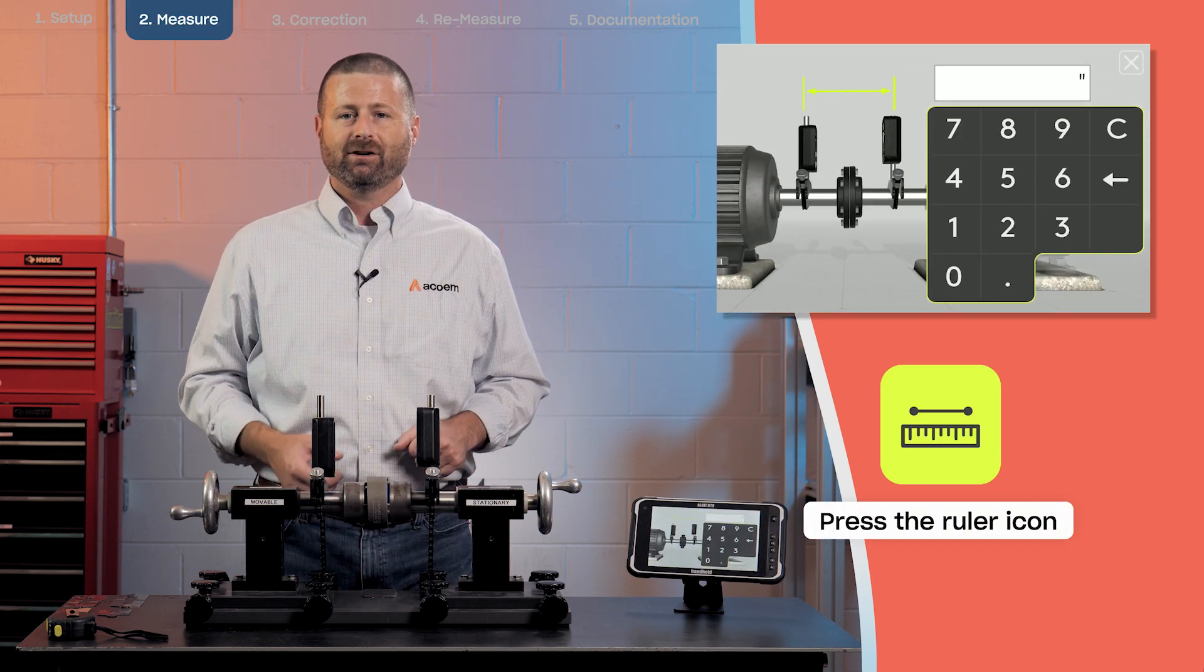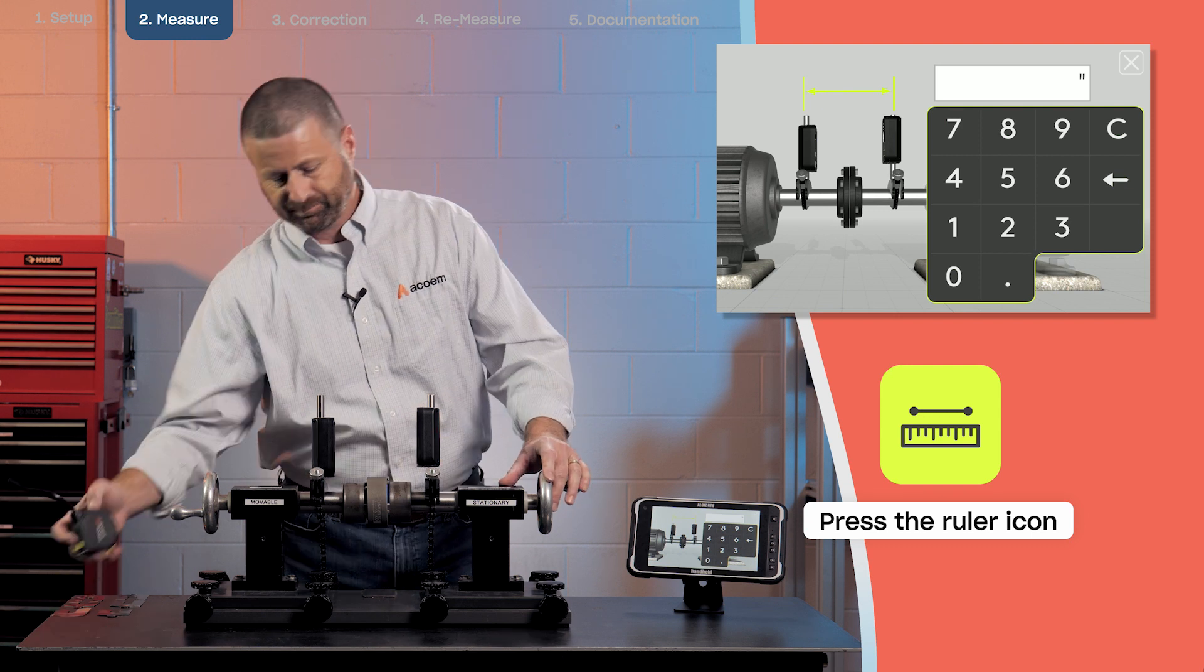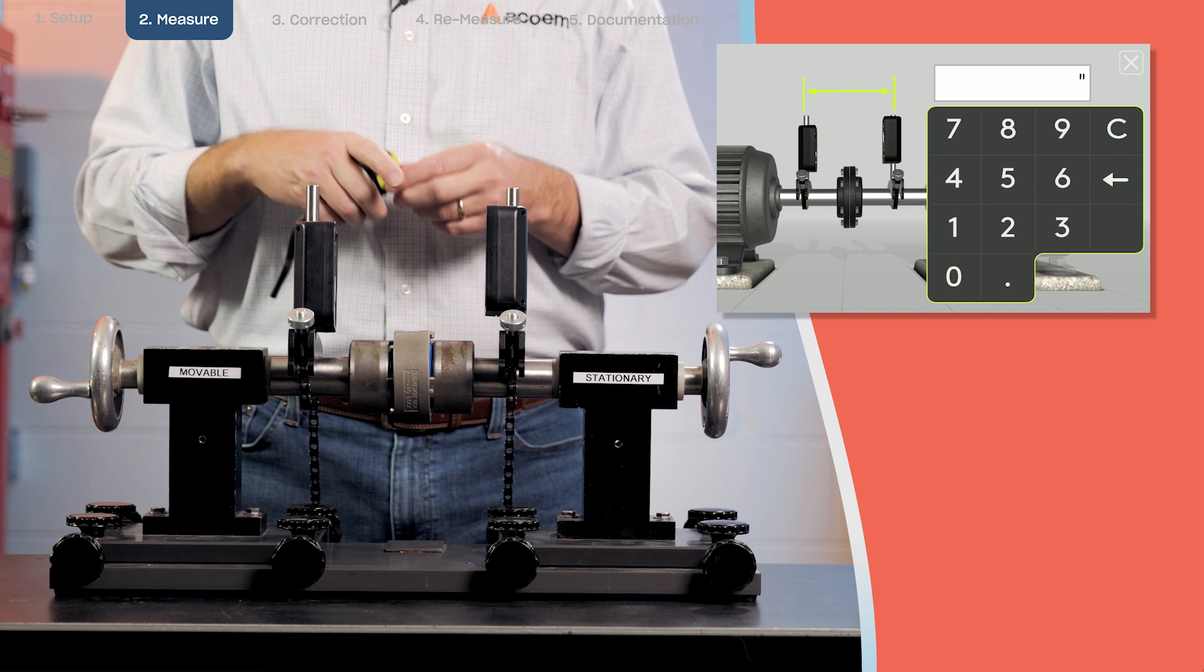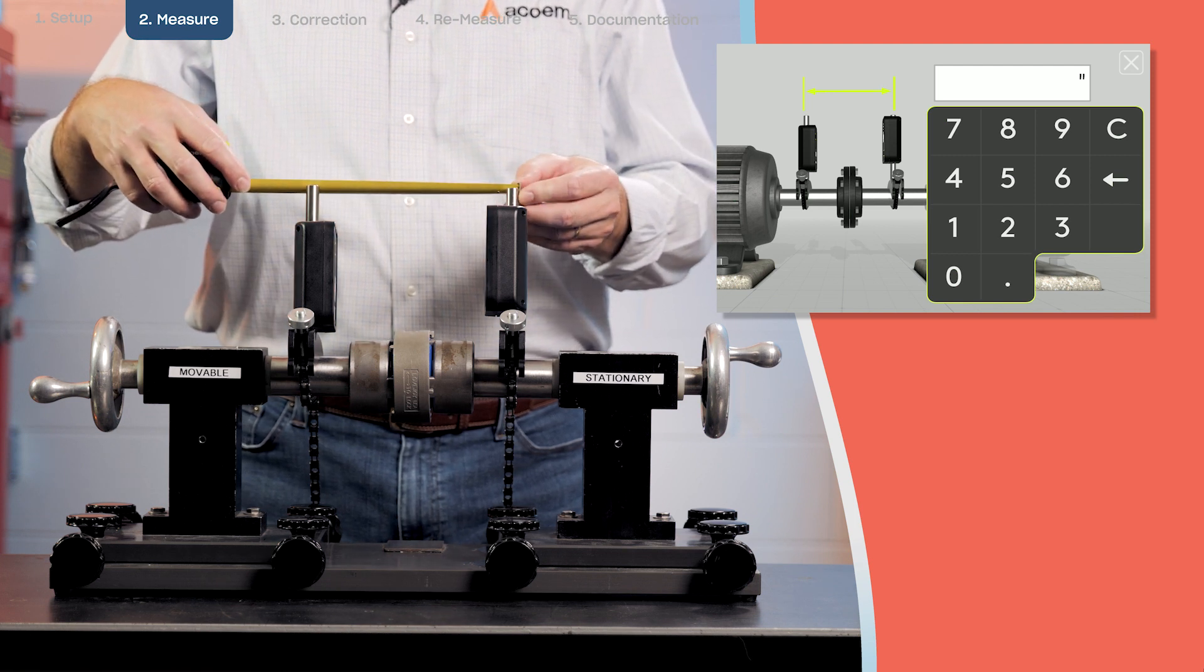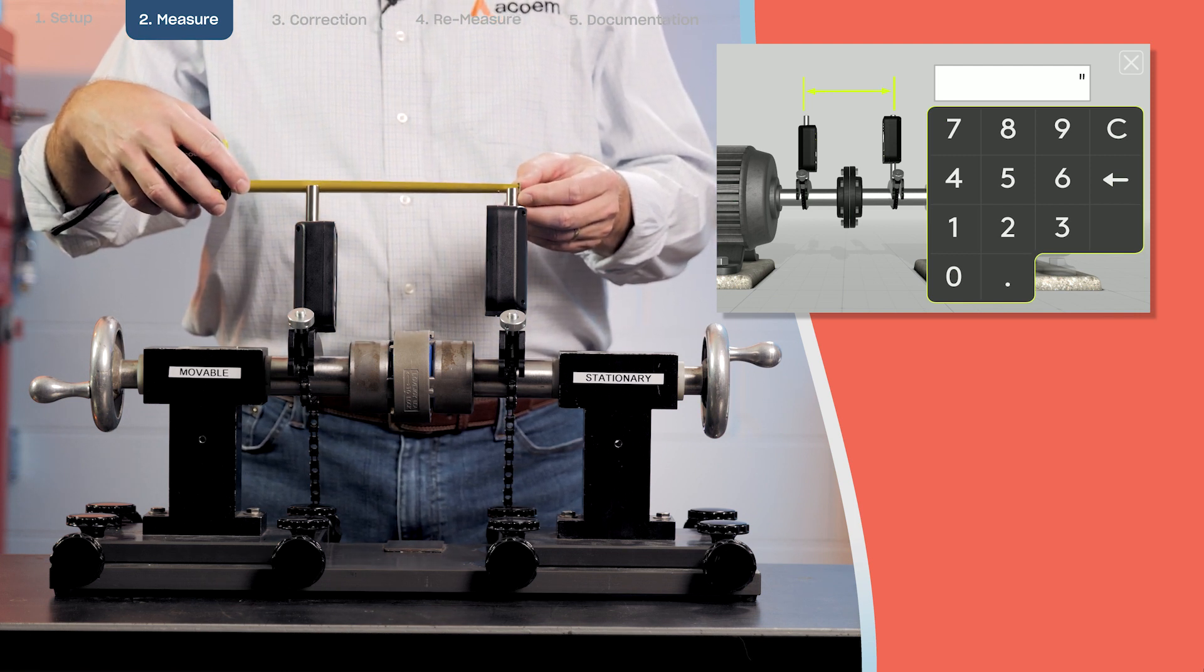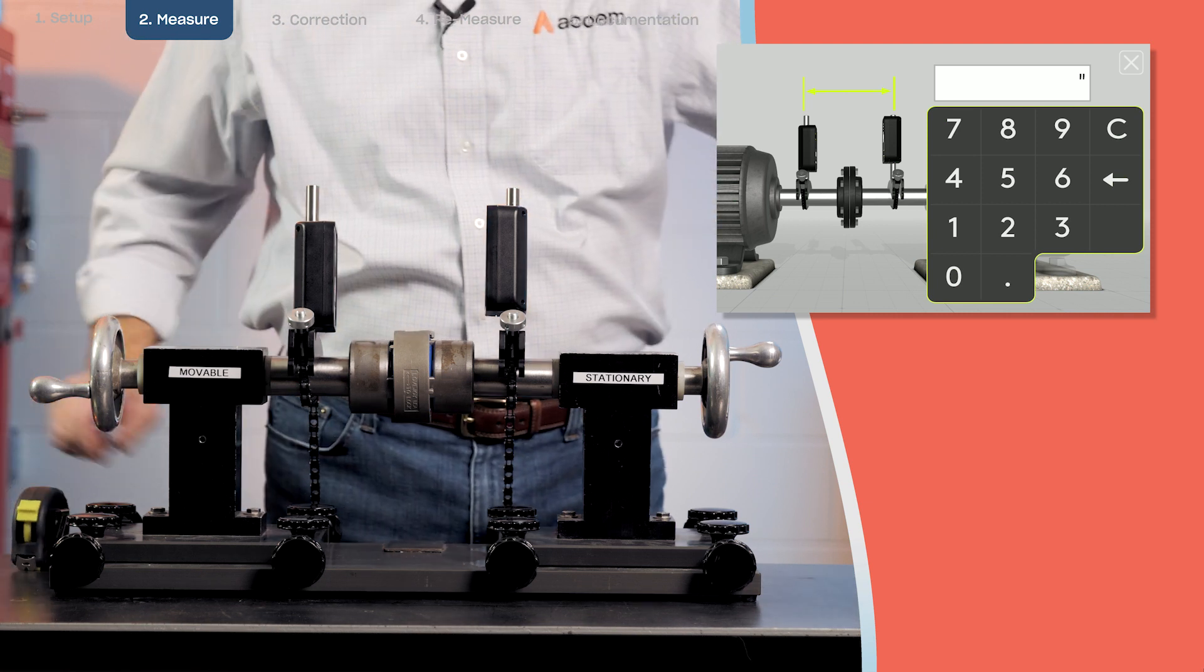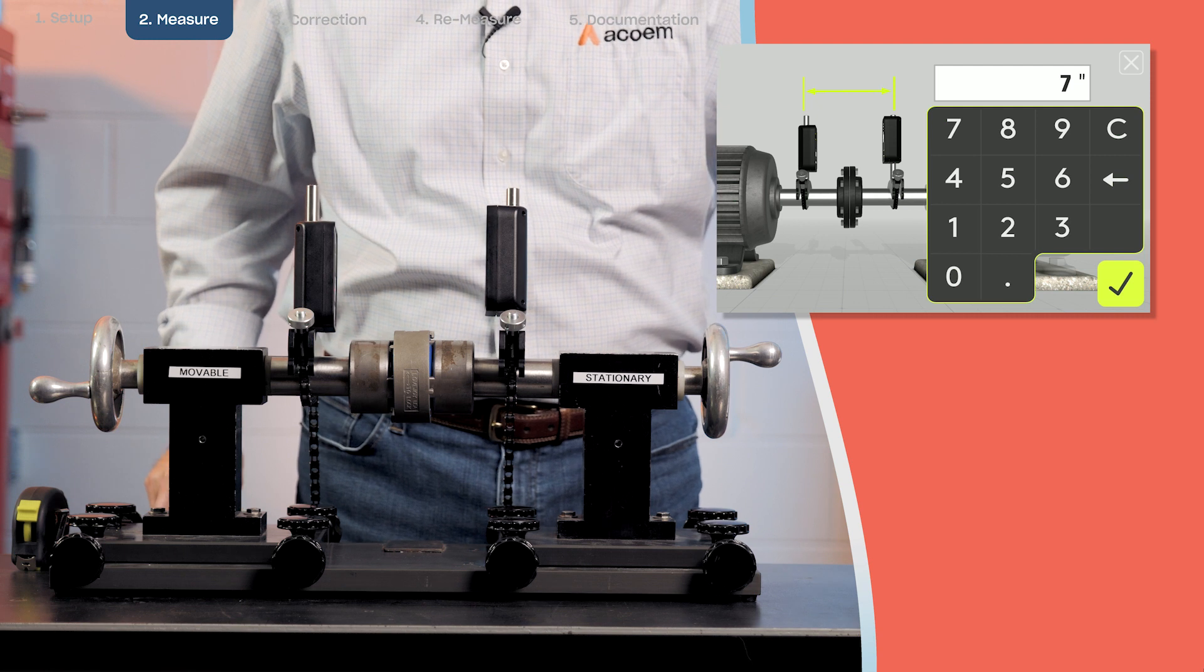Next step is going to be to enter the dimensions of the machine. First thing I need to do is enter from M sensor to S sensor. This should be done within about the nearest eighth of an inch. In this case we have seven inches. So we have seven, check.